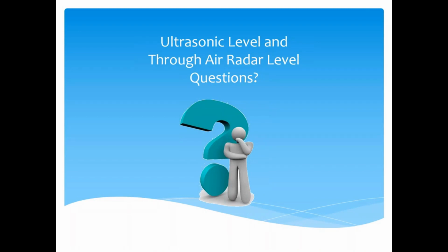Okay Ryan, so you talked about running the auto false echo suppression in an agitated vessel. Dan Vale had asked, is it better to apply that false echo suppression with the agitator on or off? It can be done either way, Dan. If it's going to be running during normal operation, which most or all agitators will be, then you should probably run that auto false echo suppression while the agitator is on, so we can get the best idea of what process conditions are going to be like while we're trying to make a measurement.